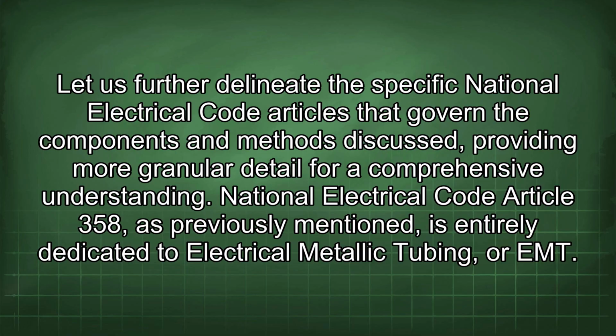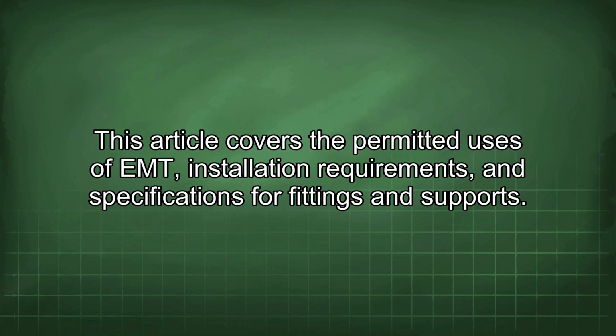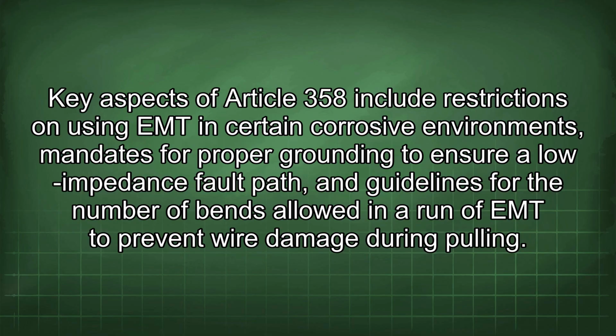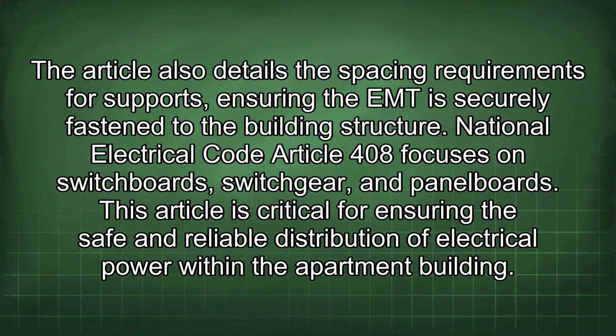National Electrical Code Article 358, as previously mentioned, is entirely dedicated to electrical metallic tubing, or EMT. This article covers the permitted uses of EMT, installation requirements, and specifications for fittings and supports. Key aspects of Article 358 include restrictions on using EMT in certain corrosive environments, mandates for proper grounding to ensure a low impedance fault path, and guidelines for the number of bends allowed in a run of EMT to prevent wire damage during pulling. The article also details the spacing requirements for supports, ensuring the EMT is securely fastened to the building structure.